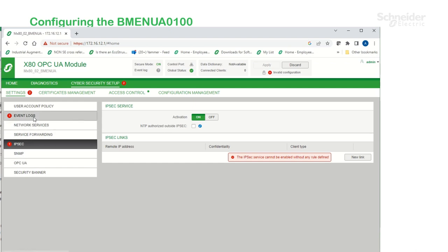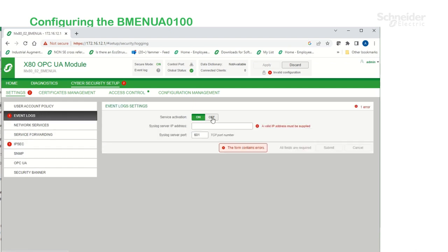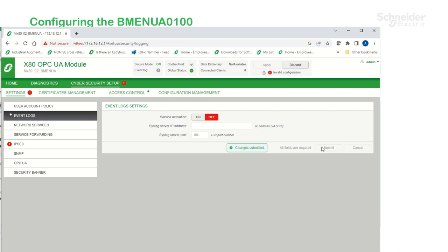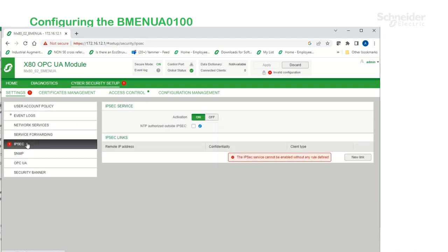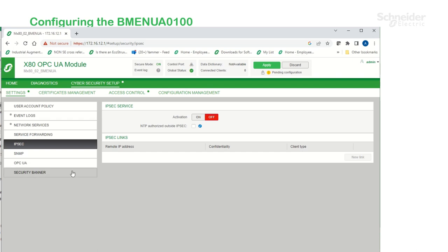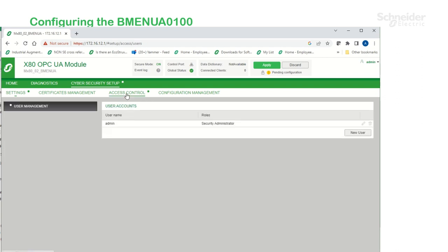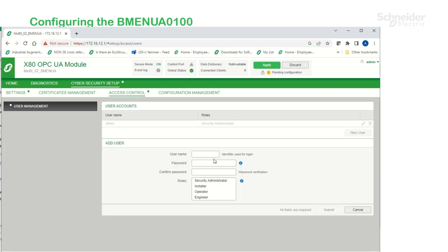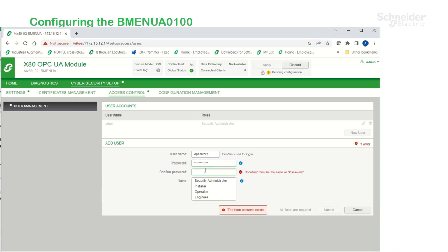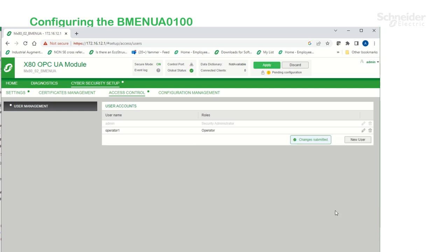I'm going to turn off event logs. Turn off IPsec. Notice the OPC UA security settings. And under Access Control, I'm going to create a new user with an operator role. Then submit and apply changes.